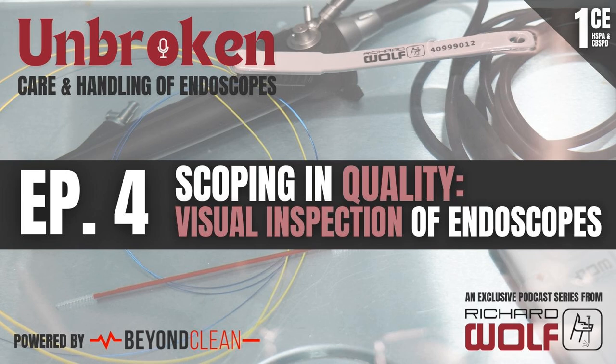Nick, in the last episode you brought up that this type of inspection actually happens at different stages and different places in the workflow. Can you speak to that? I'll make sure we hit those three letters early in the call — following the IFU. Throughout any of these inspections, make sure we're referring back to the IFU of the specific scope model you're working with, to see what the recommendations are for how to inspect it and what type of tools to use.